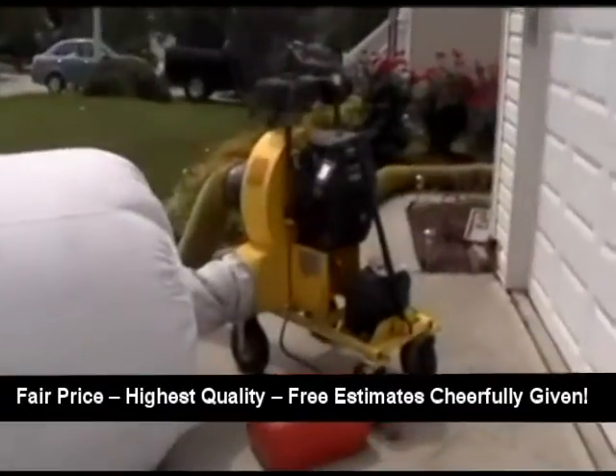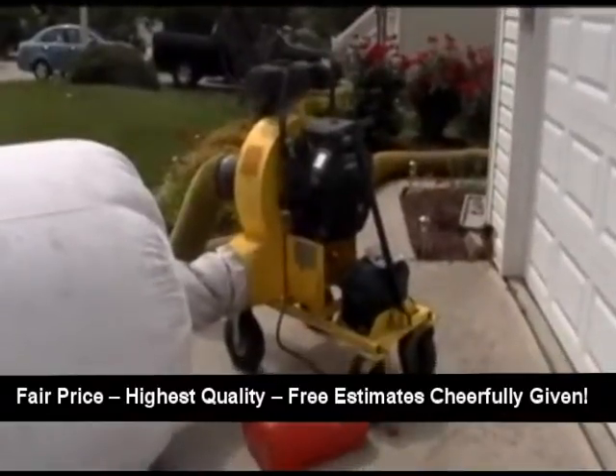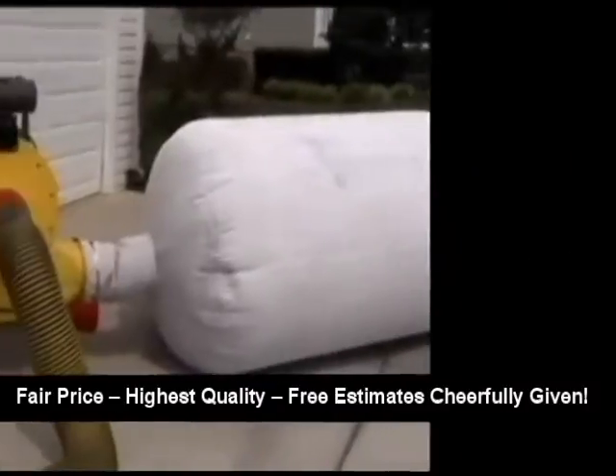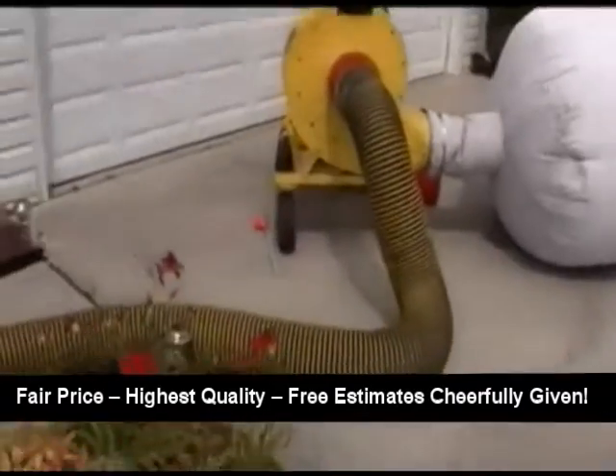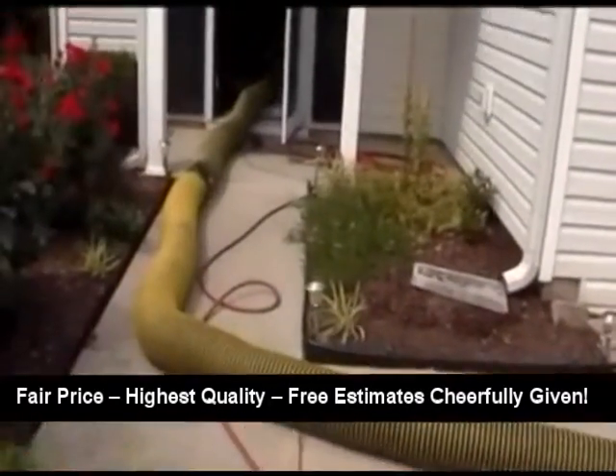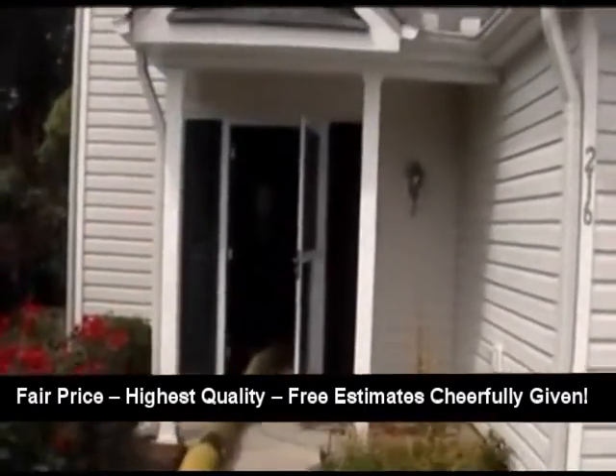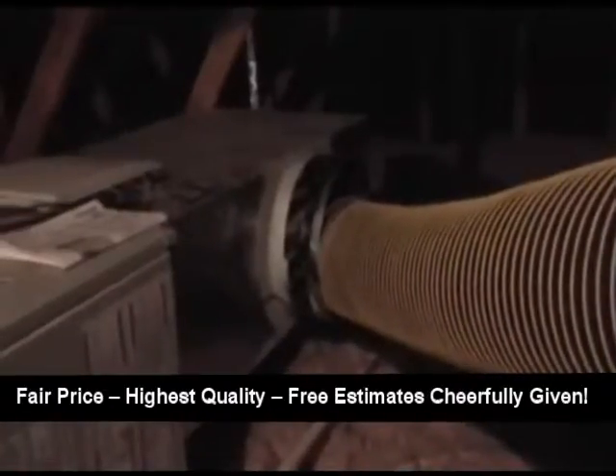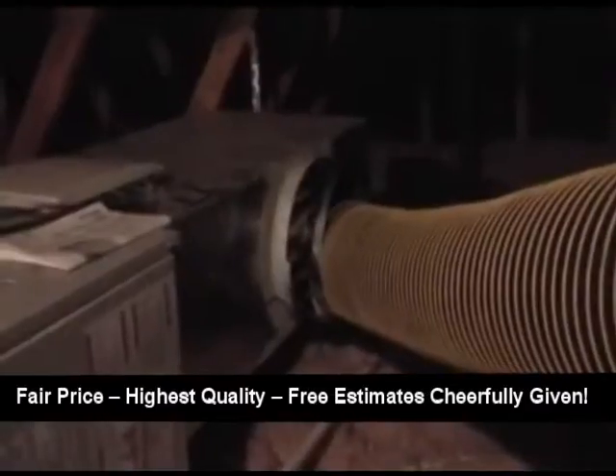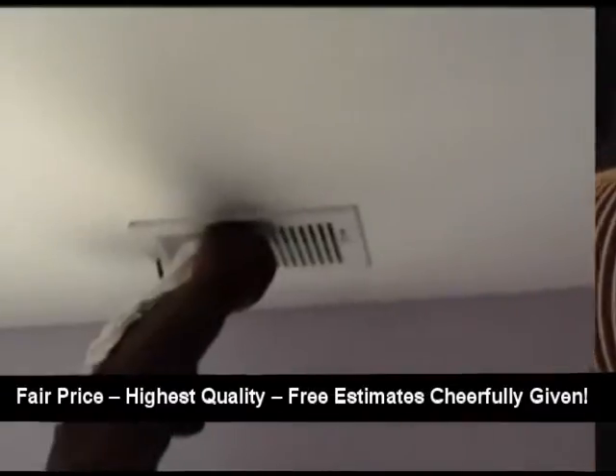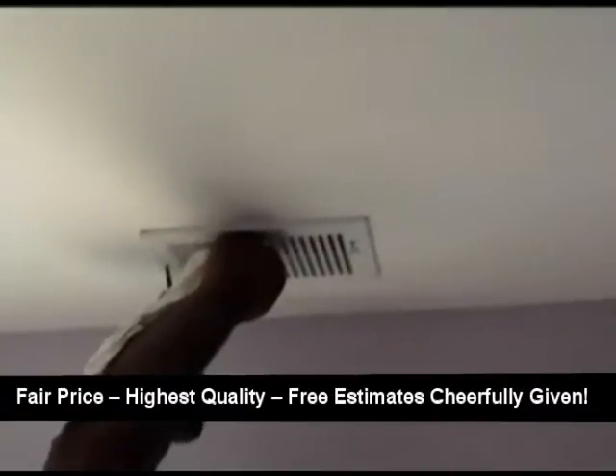We have a 25 horsepower negative air machine. We run a 10-inch in diameter vacuum line going from our negative air machine to the HVAC unit. We will fasten that to the unit and we start our machine up. When we start our machine up, it puts the whole system under negative pressure. So what that means is that when you go to all the vents associated with that HVAC unit, if you put your hand over the vents, you're going to feel vacuum on it.